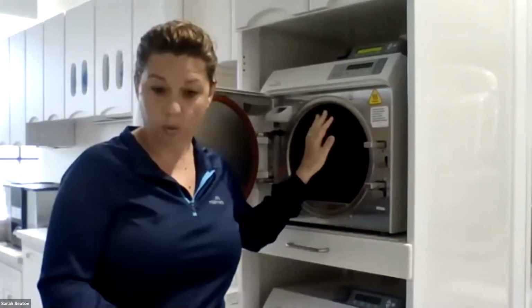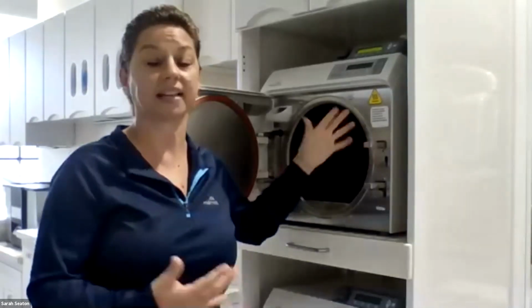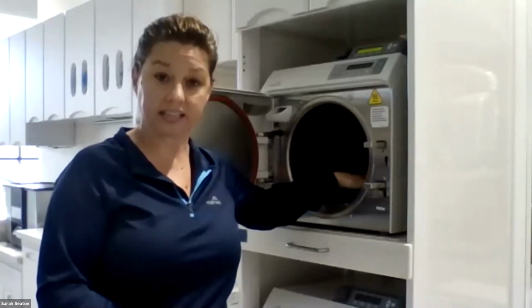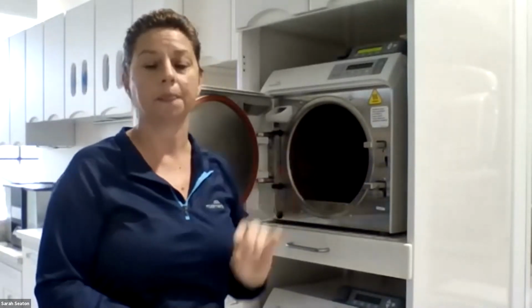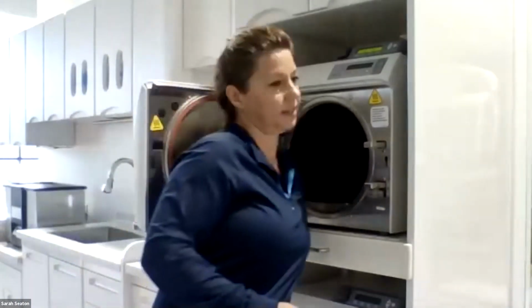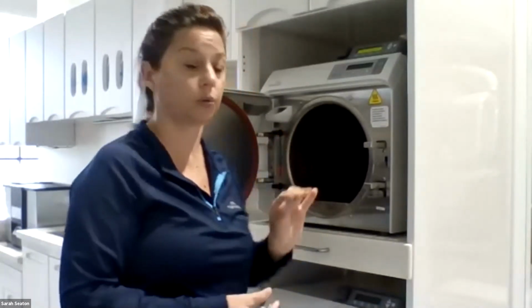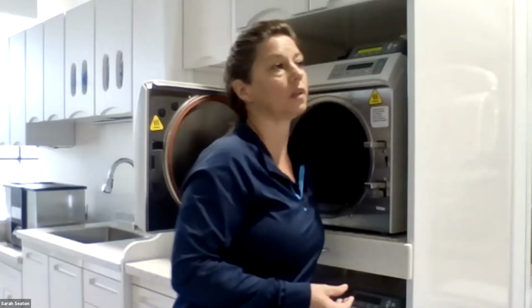It is imperative that when you're doing that, we clean the internal trays again. We want to clean the surfaces, do an in-depth clean of your trays, racking, tray plate. But not only that, we have chamber filters that need to be cleaned as well. There's 2 inside. These can be cleaned with a stiff bristled brush and speed clean, or you can throw it in your ultrasonic cleaner. Just make sure that cleaner, whatever agent you use, gets thoroughly cleaned and dried prior to reinstalling. Now there are 2 of these, so make sure you clean both of them. Those you'll want to inspect to see if they've gotten any wear or tear. They are a wear item that can be replaced. We kind of recommend annually on that.